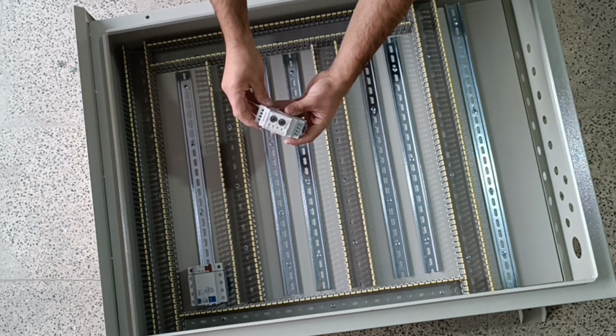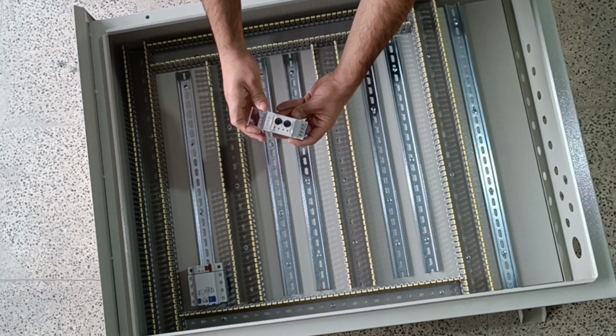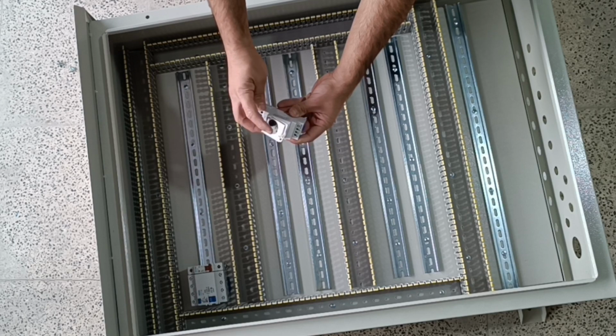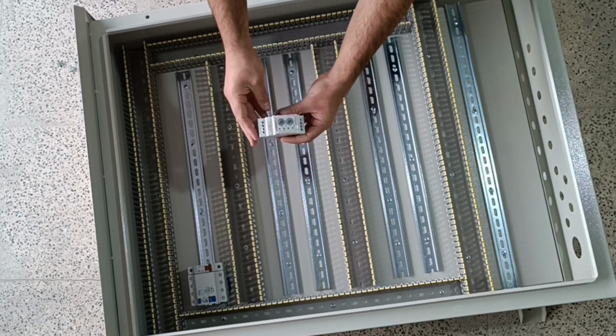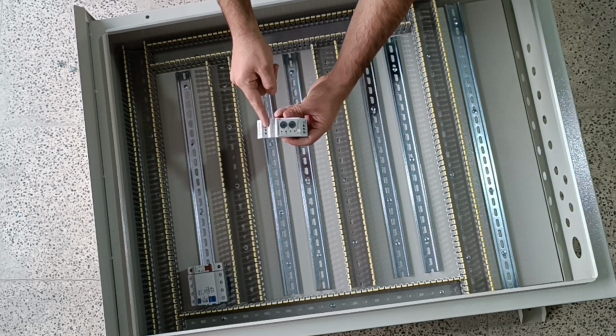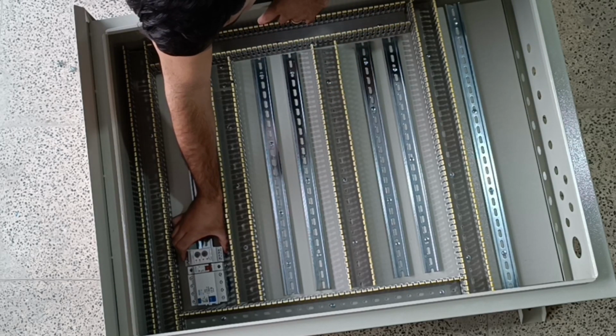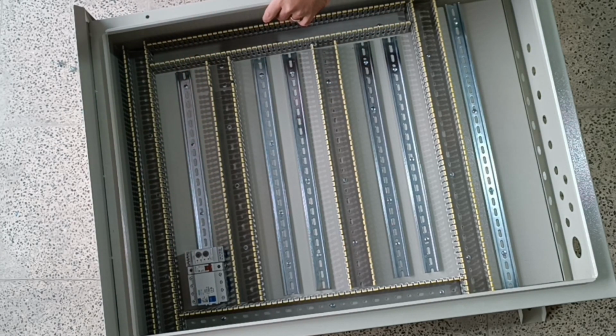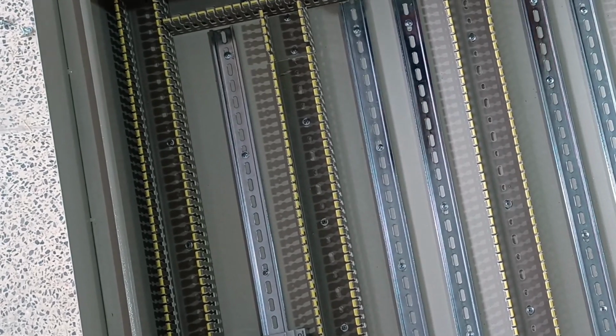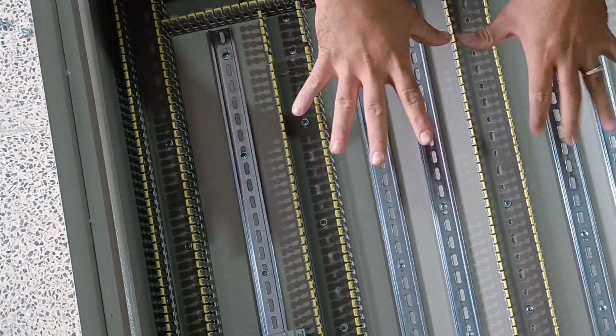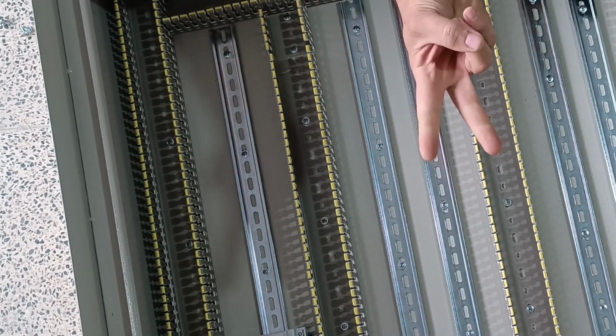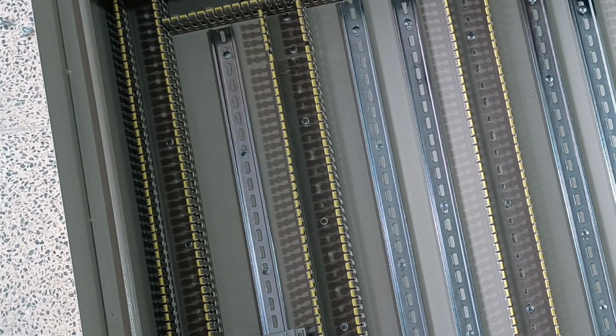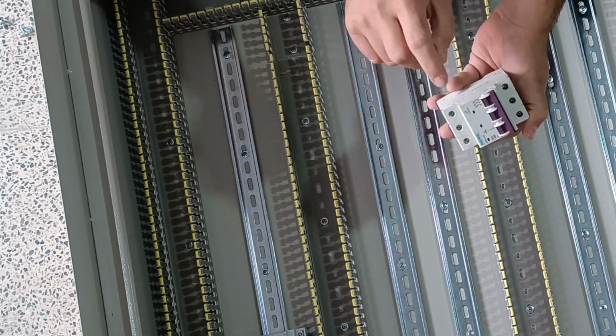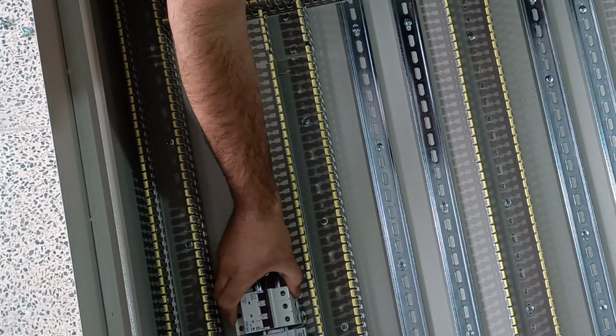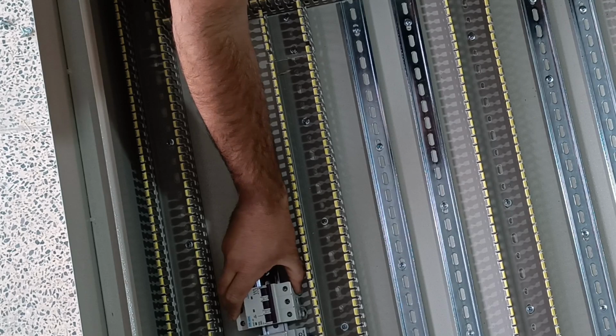This is a 3-phase monitoring relay that protects the circuit by sampling the 3-phase voltage from decreasing and increasing the voltage and damaging the equipment. It's important to use this relay in all electrical panels. In this electrical panel, there are 10 3-phase outputs, for each pair of which we install a miniature switch. These switches protect the 3-phase outputs against short circuit and sometimes against overload.